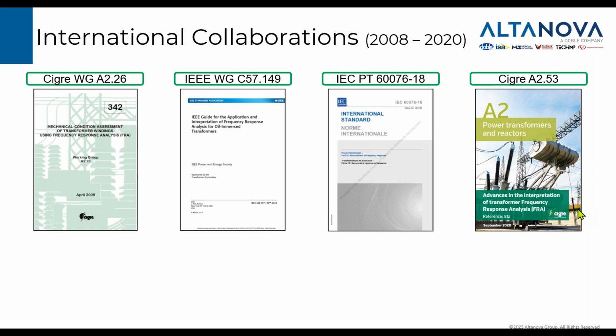It also looks at different indices that were present in the literature. We reviewed these indices and assessed them to check how effective they are and how sensitive to different types of fault. The first one is maybe less focused on interpretation, but it has more about the test technique, as it was made at a time when the technique was emerging and new products were being developed. There are 2 others: the IEEE Guide for the Application and Interpretation, and the International Standard. They both describe how the test should be done, but in slightly different manners. So if you want to follow one in your testing, you must be aware that there are different ideas presented in the 2 documents.